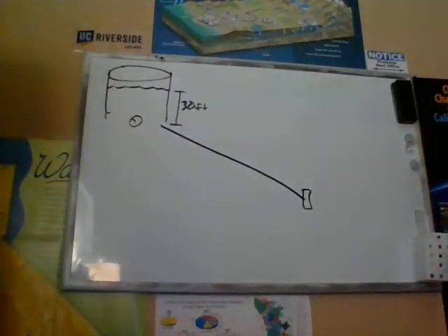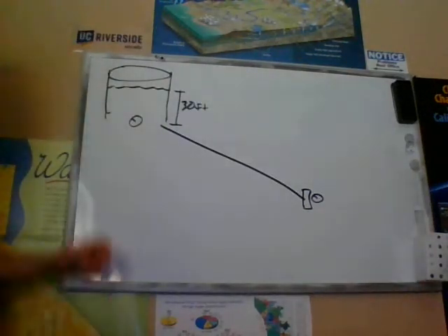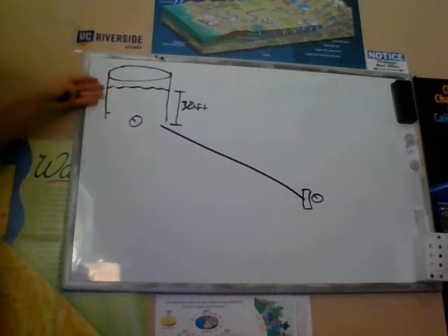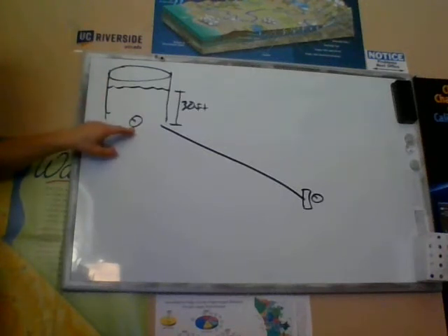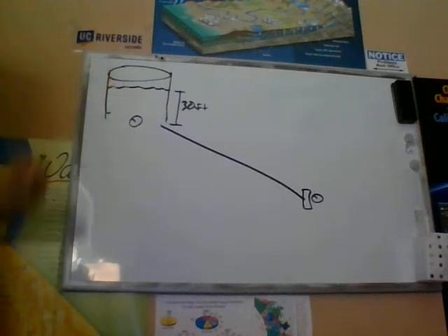And then we're going to think about a fire hydrant that's down here. And with this fire hydrant, we're also looking at what is the pressure down at that fire hydrant. Now, the information I'm given in this problem is what is my height of water in my reservoir. That's going to give me a certain amount of pressure at this point because of that head. 2.31 feet of head is equal to 1 PSI, or 1 pound per square inch.